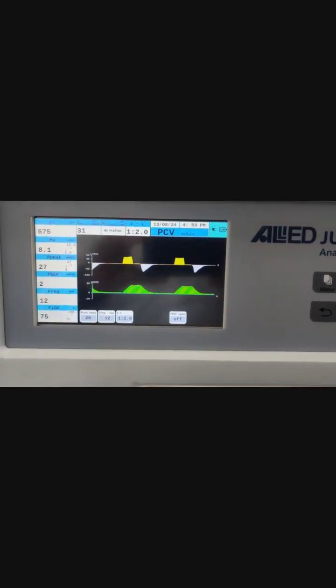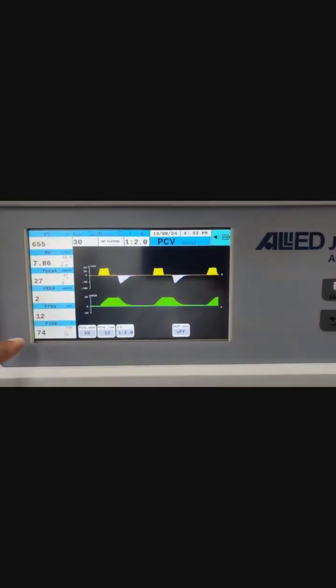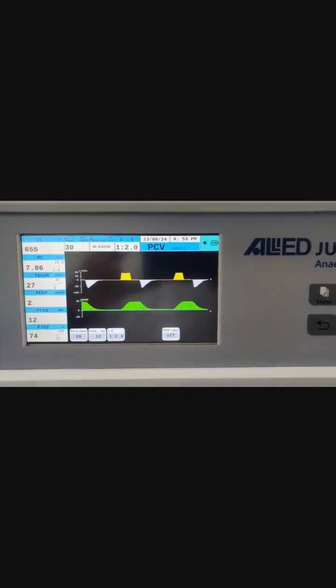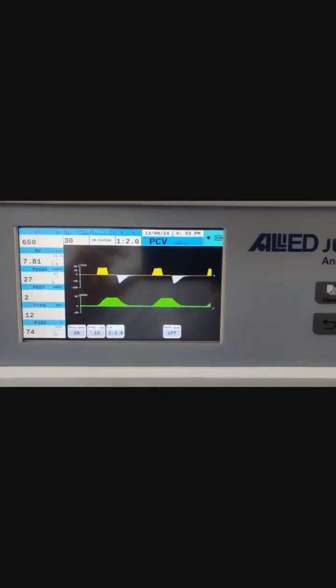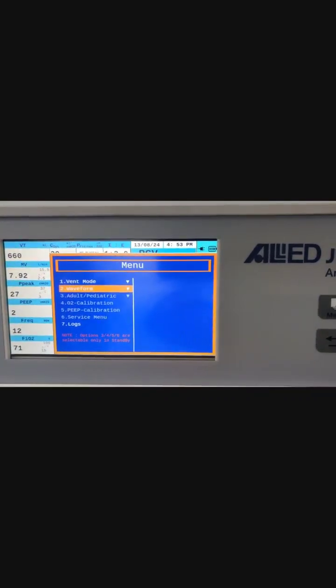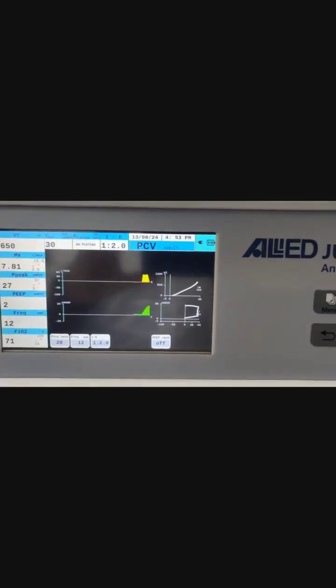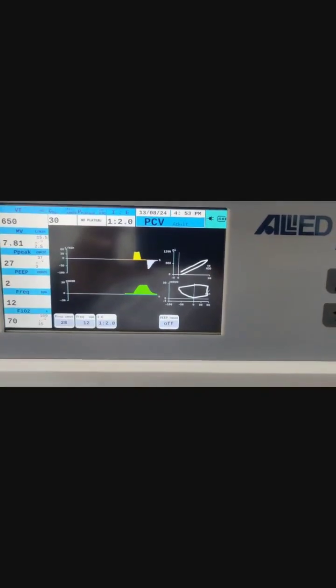So this is the condition when the machine is running. We will be getting 2 waveforms. One is flow versus time, and the second waveform is pressure versus time. And if you want to see the spirometry loops, that option is also available. In the waveforms you have to go and select the loops facility, then you will get 2 loops. One is volume versus pressure and the other one is pressure versus flow.